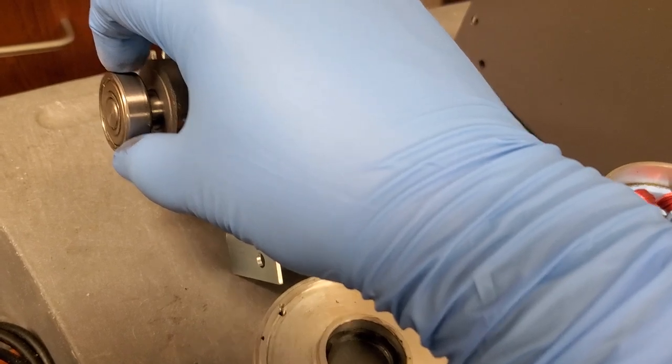I don't know if you can see that, but it is wobbling. When it wobbles, you have right here your permanent magnet for the motor, and your magnet will start to wear on your stator. It will rub, it'll etch, and it creates this really fine dust that gets all over everything.